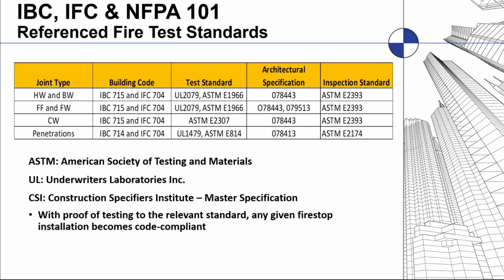Head of wall and bottom of wall have International Building Code 715 and International Fire Code 704, and they have test standards UL 2079 and ASTM E1966. They are also specified in architectural specifications in a building design. The specification section in this particular case is 078443, which would be fire stopping for joints. Then there is also an inspection standard that building inspectors use to review the documentation in the structure and make sure that it meets the proper test standards, and that is ASTM E2393.